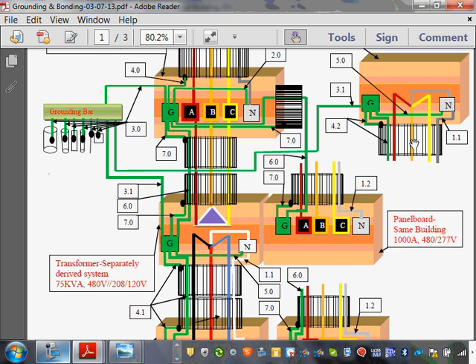In a generator that size, most likely it will be inside the building and tied to the grounding electrode system. If your generator is outside and you're tying solely to the ground rod, the code still says you do not have to go larger than number 6. There is nothing that I know of that says a separately derived system is an exception. Anybody seen anything? Nothing that I know of. Most of the stuff I was involved in, we don't do the driven rod. They're bigger systems. But anyway, if you get up to 6 or larger, for most of the smaller generators, 6 will be good enough from sizing.